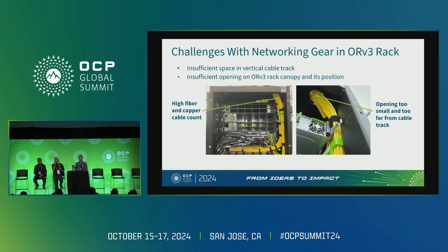The second challenge is cabling. The first version of ORV3 had the same canopy cutouts as ORV2 — this was at a time when compute had a smattering of cables coming from outside the rack, maybe eight LC duplex fibers and a handful of CAT6 or CAT5 cables for console management. But for network, we're talking up to over 2,000 fibers coming into this rack. So we knew this wasn't going to scale — the canopy cutout was too far over and too small. That's going to need to be addressed in order to accommodate network.